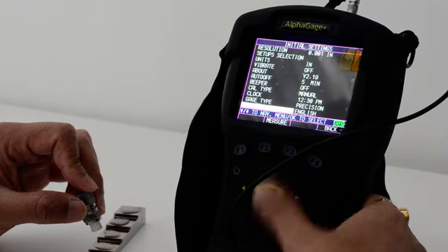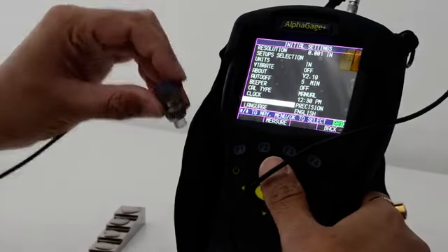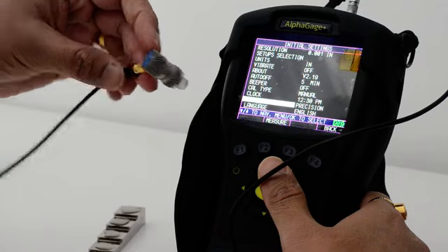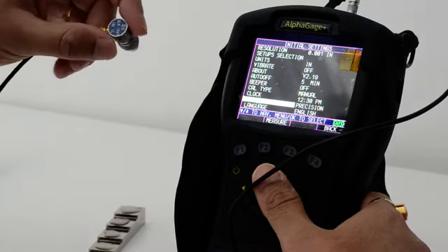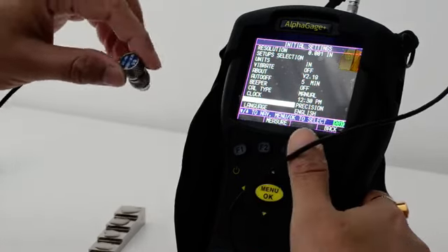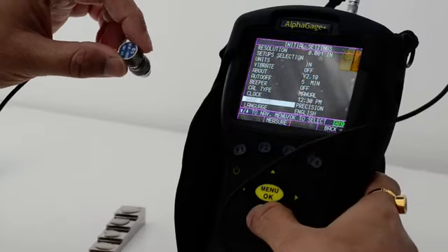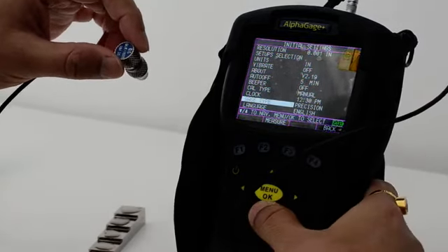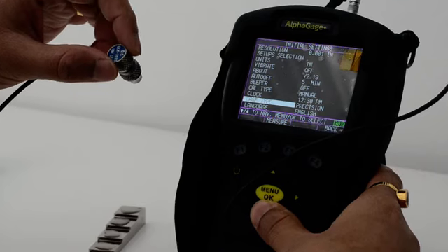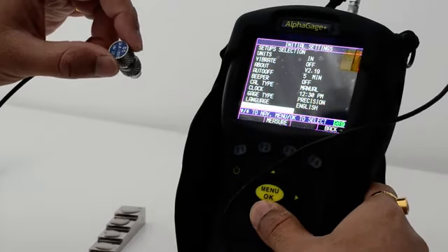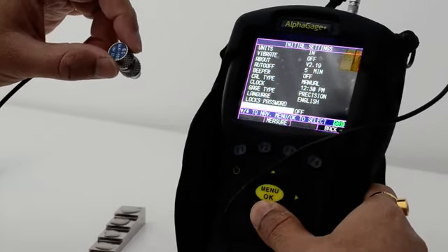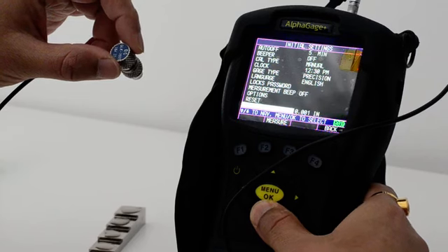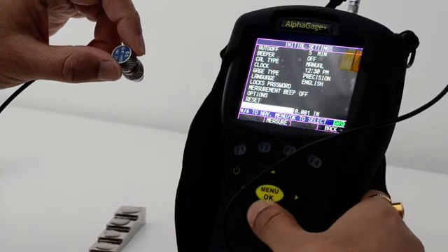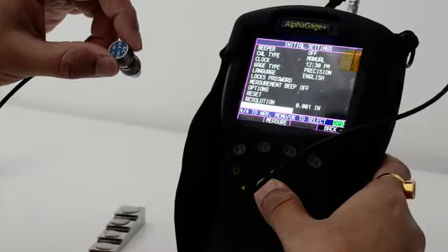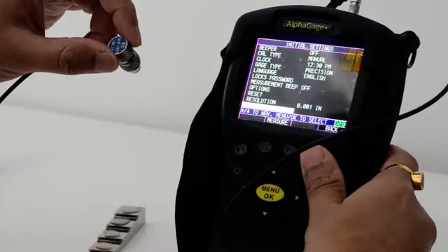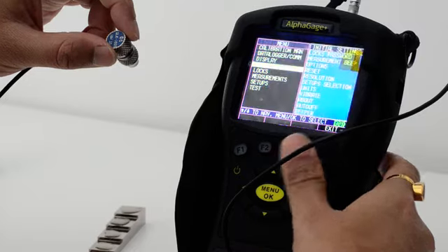You can select the gauge type. Right now we are doing precision, so we are using precision. Precision means it's a single cable. So in the gauge type, you have to select the precision mode. If you are using a dual corrosion probe, then you have to select the gauge type as corrosion. The language, you can select many languages. There is English, and there are options, reset, resolution. Yeah, so coming back to resolution again. So these are all in the initial settings.